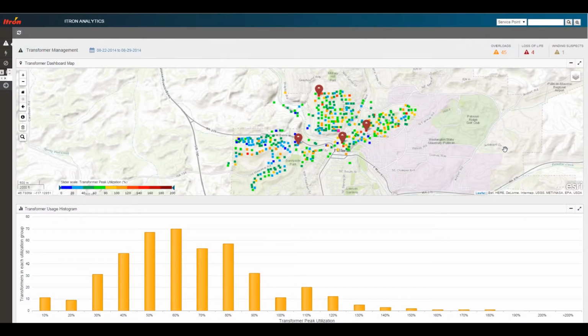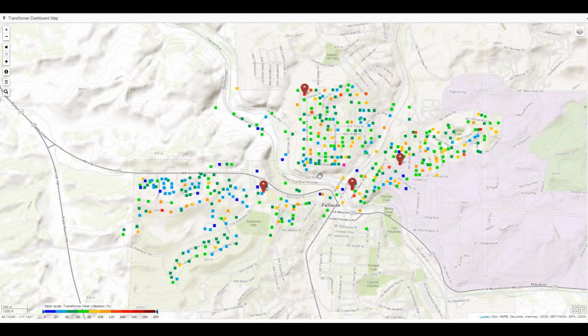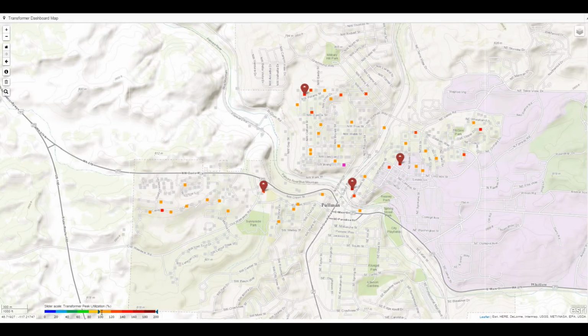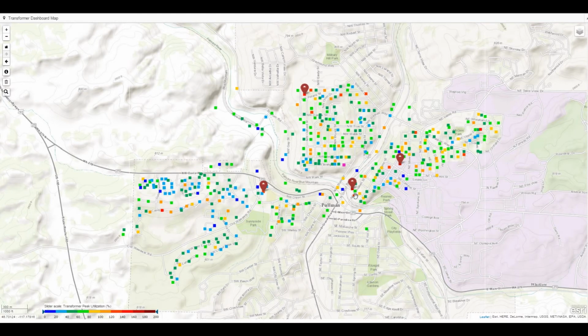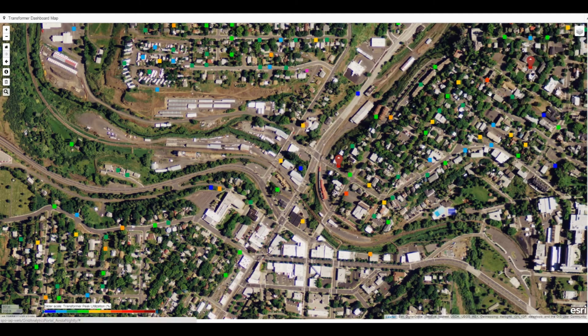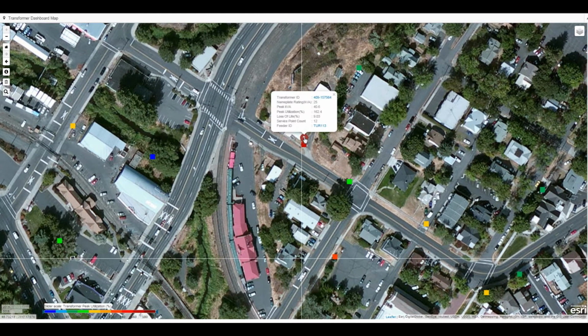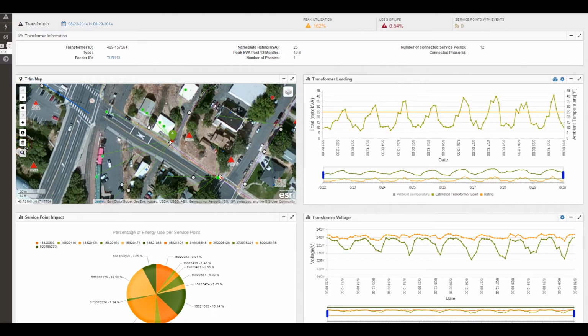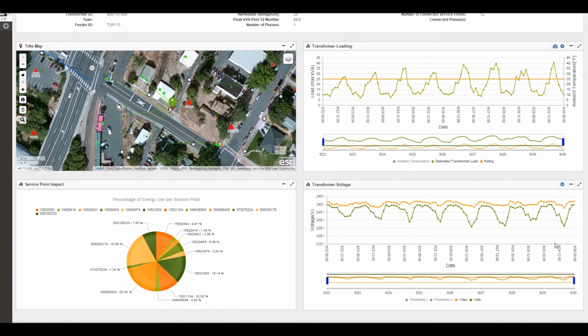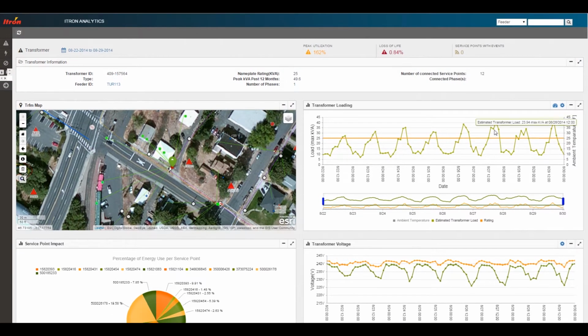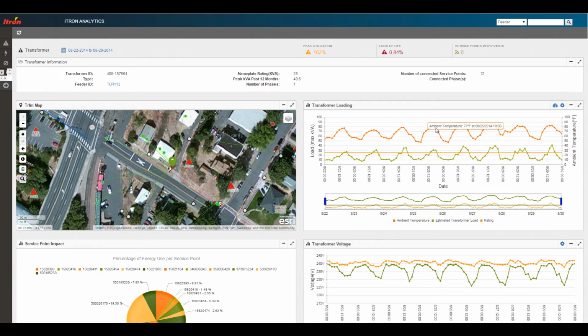The Transformer Load Management Dashboard provides an overview of the planner's area of responsibility. Key performance indicators summarize overloads and provide quick access to a list of overloaded assets. Markers indicate distribution transformers that have exceeded nameplate loading or have experienced significant loss of life. Zooming into a specific area provides the planner with granular visualization of load on all transformers by a color-coded heat map. A slide control allows the planner to view specific load ranges to target either under or overutilized transformers. The planner then drills into detailed loading and voltage information for any transformer or its connected service points, giving him or her detailed insights about its utilization and loading condition. In this scenario, one service point is responsible for the majority of transformer overload.